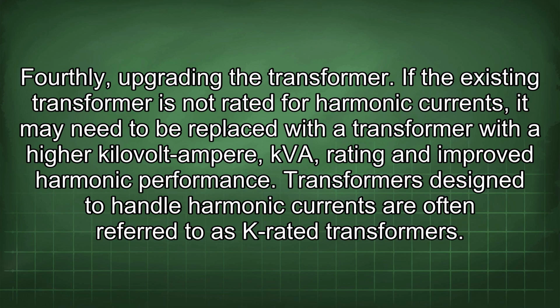Fourthly, upgrading the transformer. If the existing transformer is not rated for harmonic currents, it may need to be replaced with a transformer with a higher kilovolt-ampere (kVA) rating and improved harmonic performance. Transformers designed to handle harmonic currents are often referred to as K-rated transformers.